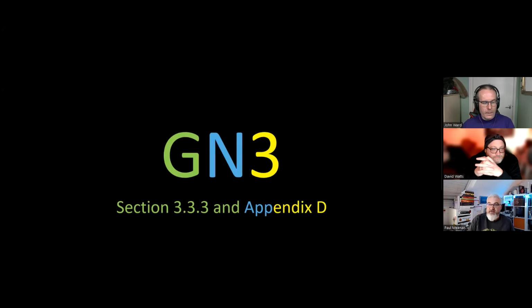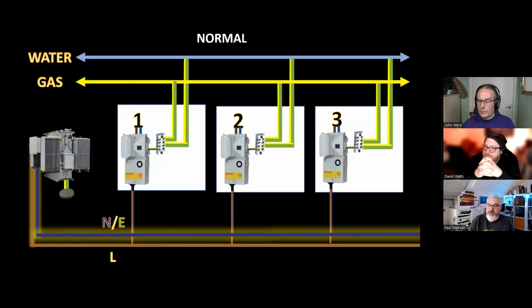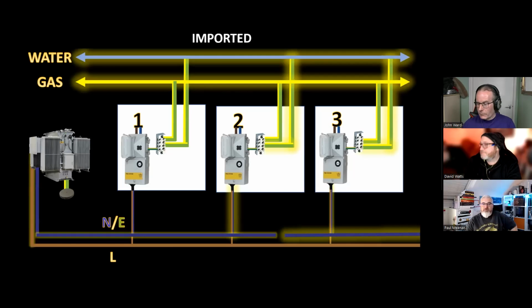So I've already found a couple of errors and I'm only on day 2. It basically covers safety checks, which are really important, which is why we did our podcast. I'm not going to bore you with this. You've seen this in our podcast, but basically this is a CNE network or a PEN network, TN-C-S supply. If you get a broken neutral, it can basically be like this. I can't read the words at the top. But basically this configuration is normal. This is where you export. So for instance, with a broken PEN, you go from 3 into 2.